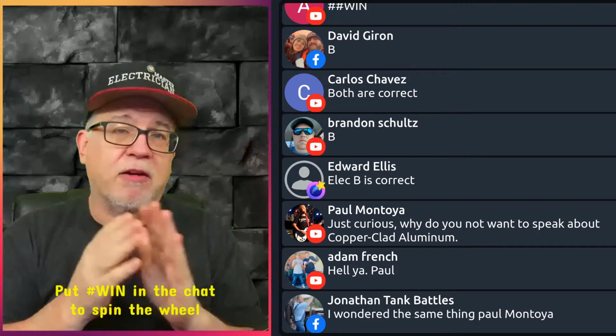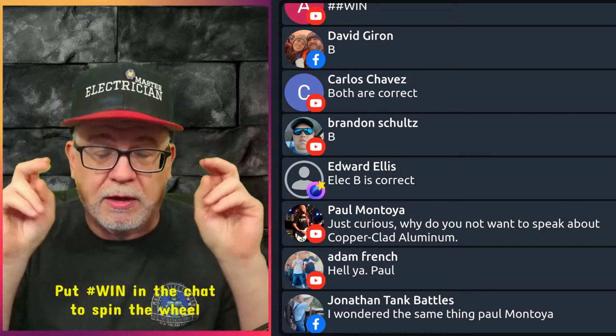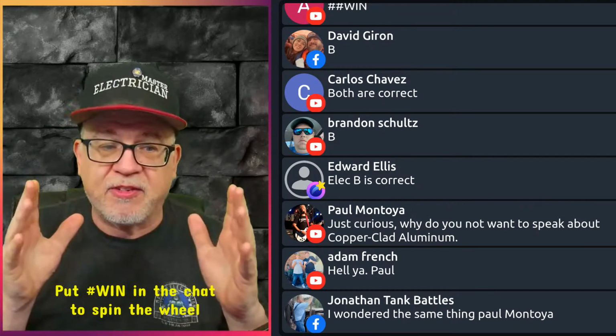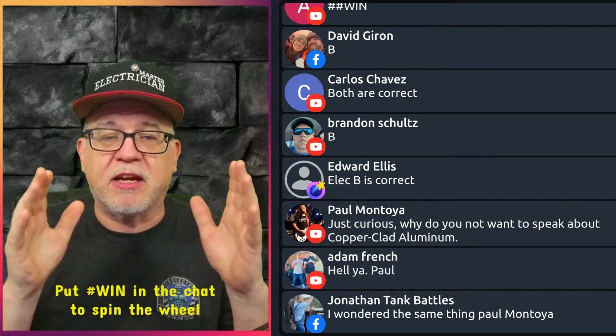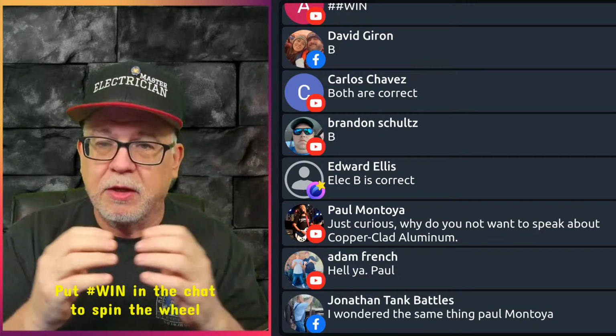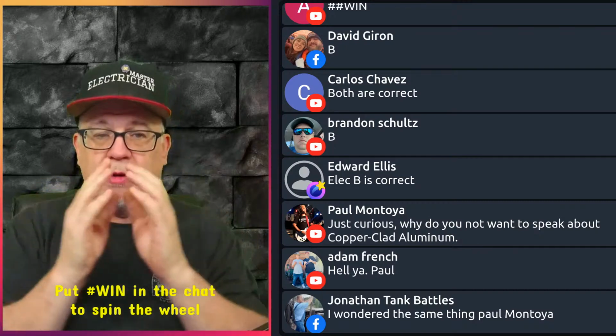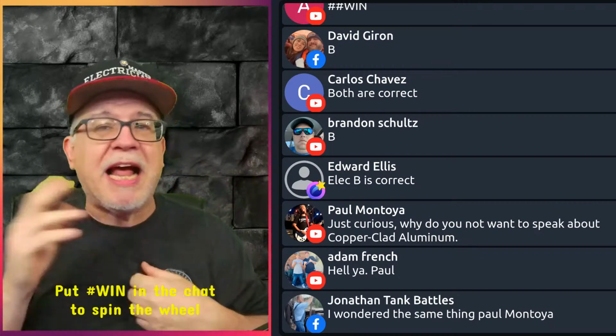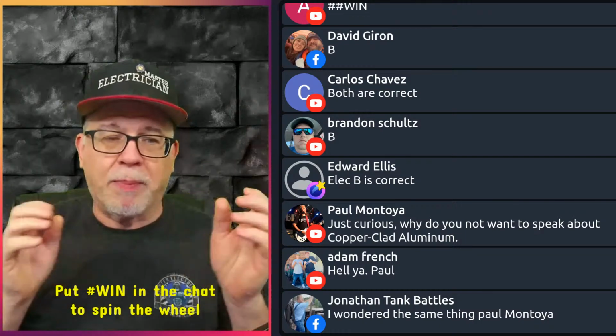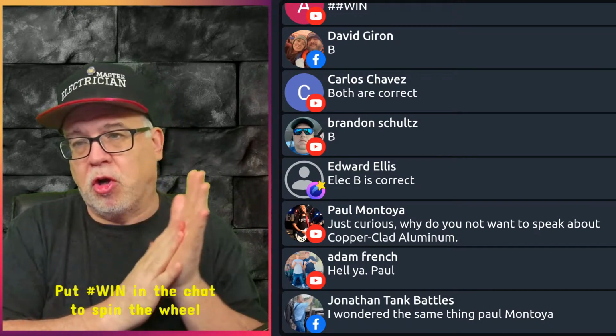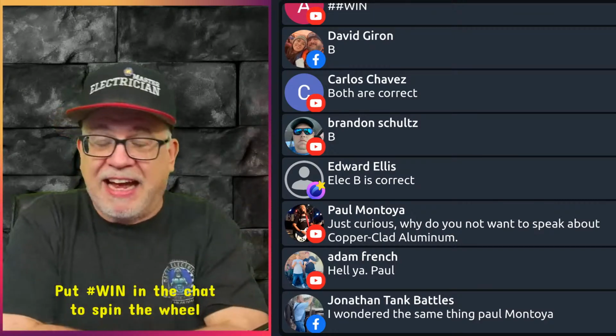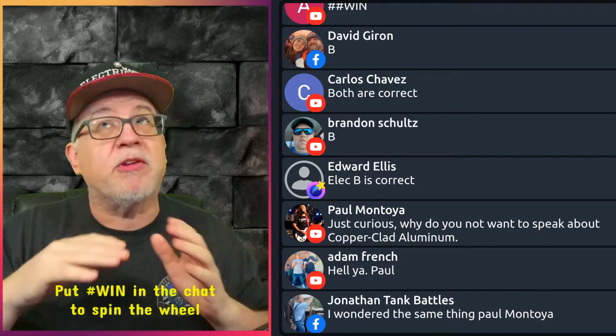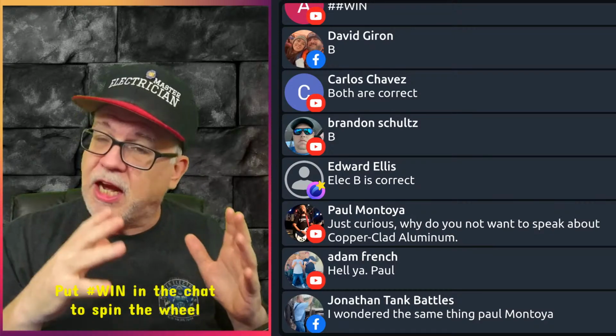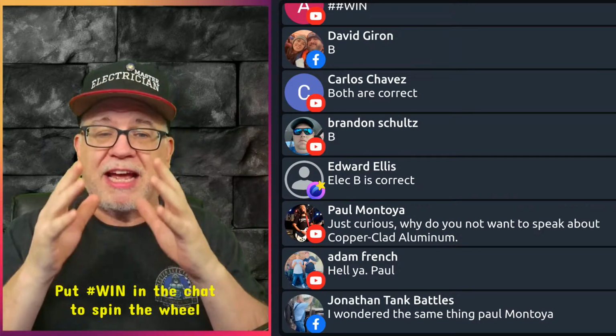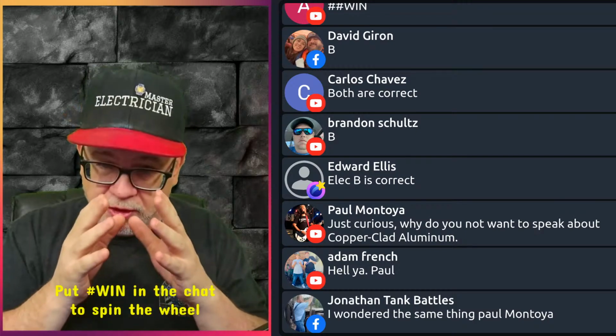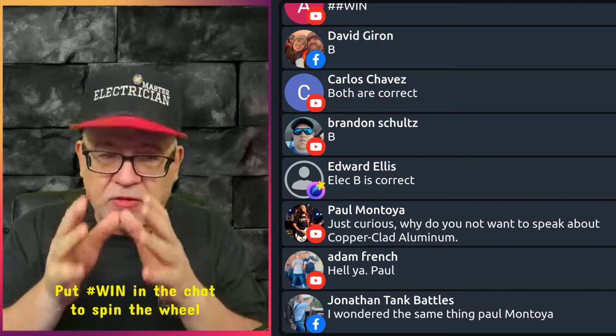Now, nothing says that I can parallel that like we normally parallel. And when I say that, it means taking 10 sets of ungrounded conductors to get a certain amount of current. That's why we're paralleling, okay? We need to run more sets so we don't have to run one big conductor. We run smaller conductors to get the same amount of current. Well, we're not doing that with an equipment ground. That's not why we're paralleling, okay? And so you run full size. Well, if that's the case, up until 2026 gets published, the concept is that you could have an equipment grounding conductor that is larger than any of the ungrounded conductors or grounded conductors in a specific raceway.